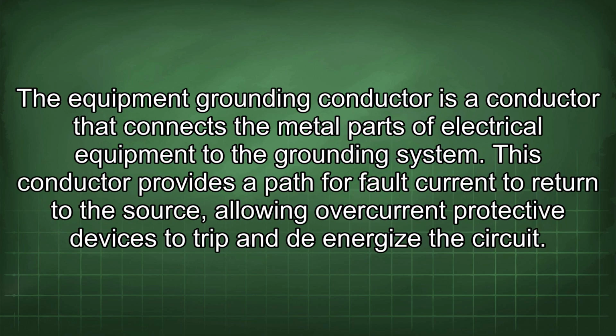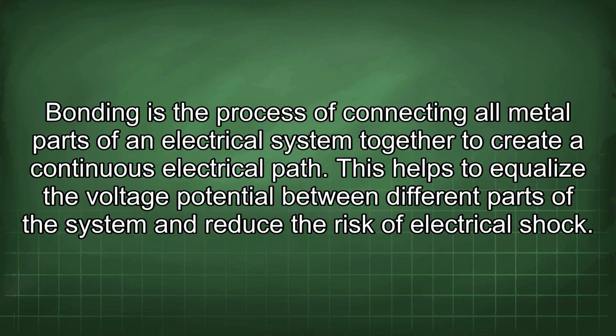The equipment grounding conductor is a conductor that connects the metal parts of electrical equipment to the grounding system. This conductor provides a path for fault current to return to the source, allowing overcurrent protective devices to trip and de-energize the circuit. Bonding is the process of connecting all metal parts of an electrical system together to create a continuous electrical path. This helps to equalize the voltage potential between different parts of the system and reduce the risk of electrical shock.